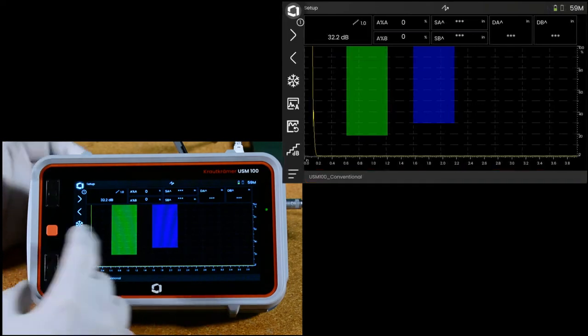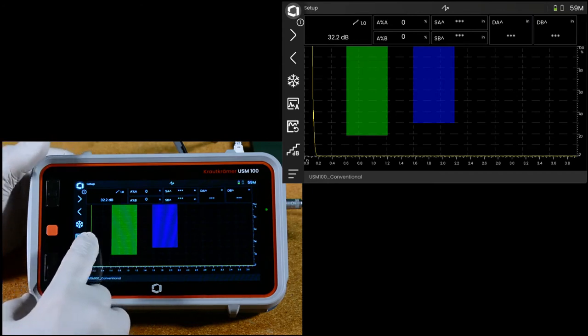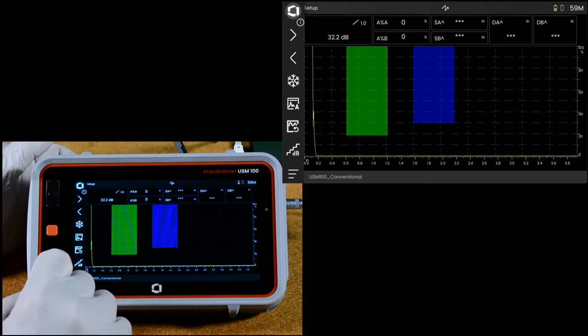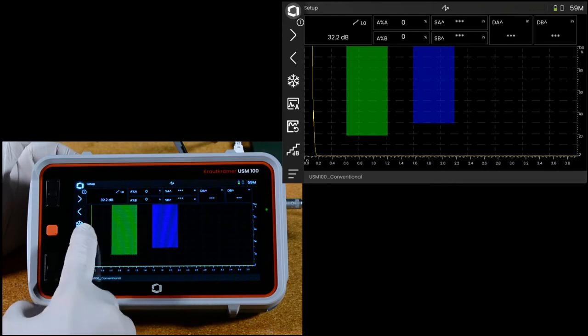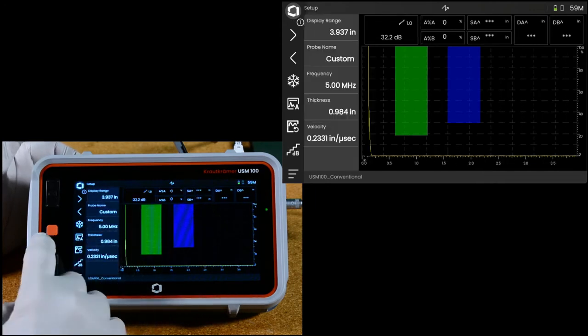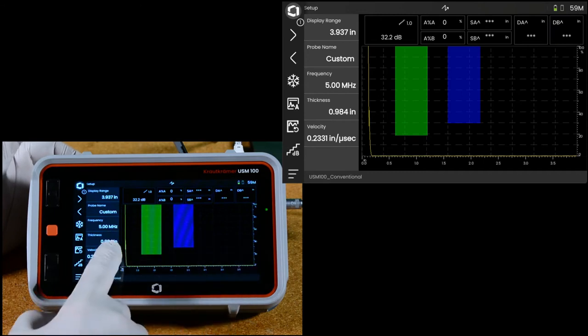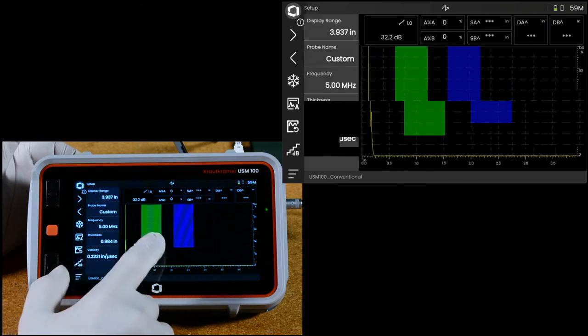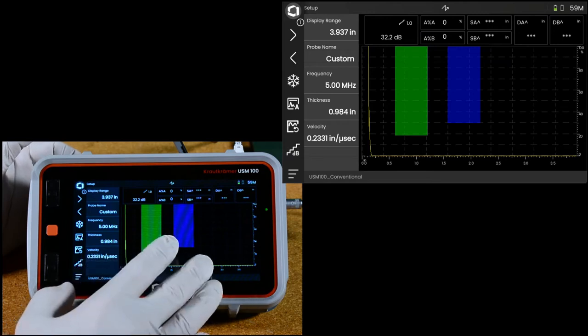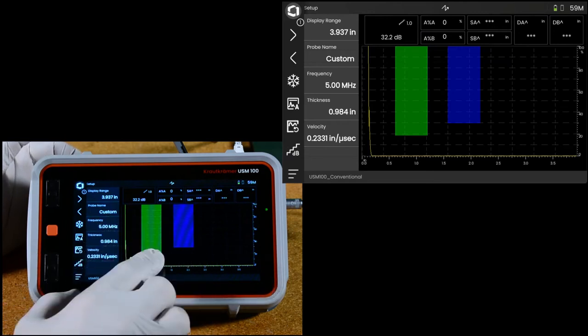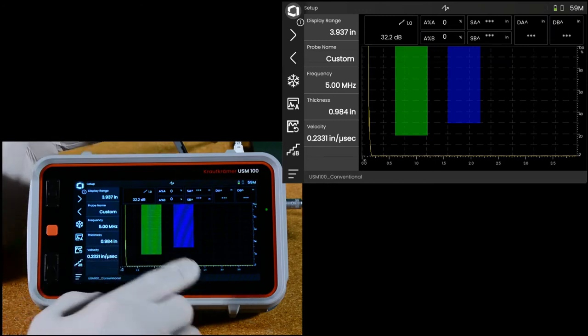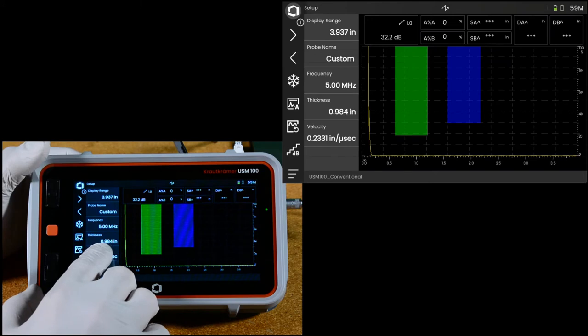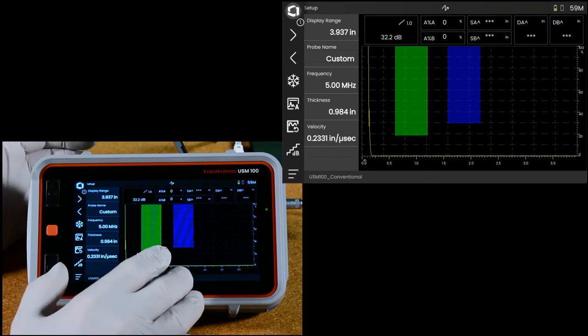The next feature of the instrument is that each panel of the app will have a special sidebar menu. The sidebar is accessed by pressing here at the left edge of the A-scan and swiping your finger to the right. The sidebar is put away by just putting your finger down somewhere in the sidebar and swiping it back to the left. So swipe it out and you get a menu that is custom for each one of the panels of an app. There are some default menus based on the panel type, whether it's calibration, inspection, what have you. Or the app author can add controls to this or hide controls, whatever makes sense for the app.